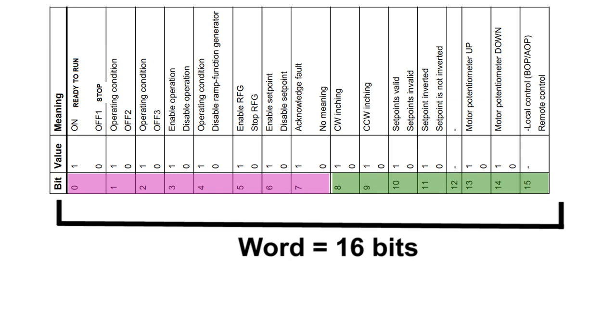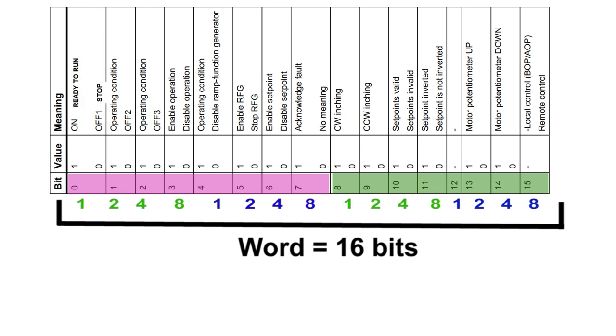One word consists of two bytes, each containing 8 bits, marked with pink and green color. Each bit has a specific function. For example, if bit 0 is on, this means the VFD should run — this is the run command. If bit 0 is 0, the VFD will stop. Each bit has a specific value in the hexadecimal system. To run the motor in the forward direction, we have to send the code 047F to the control word.